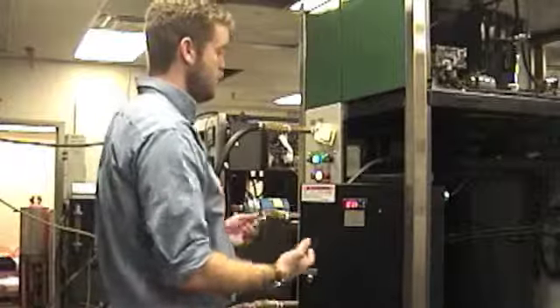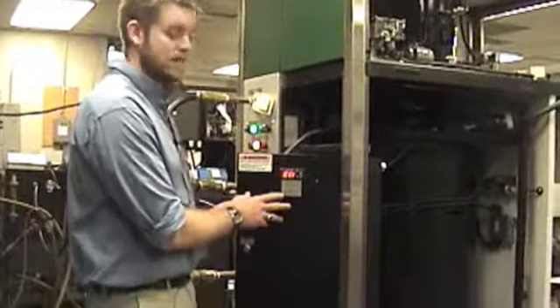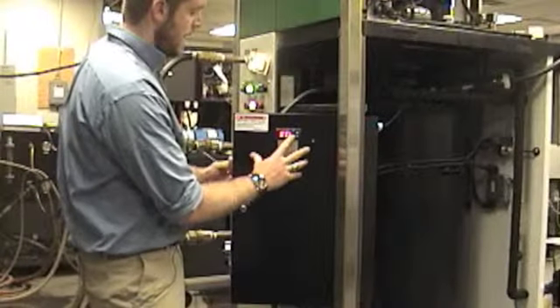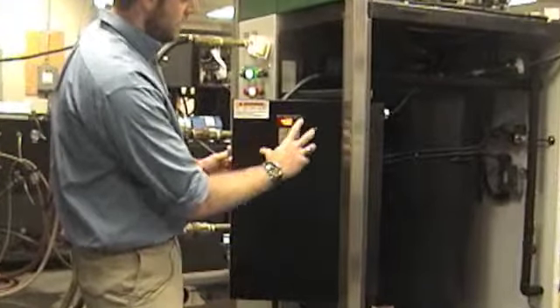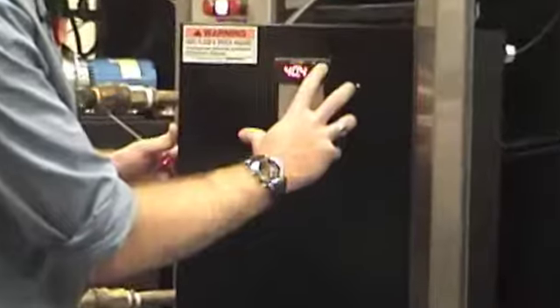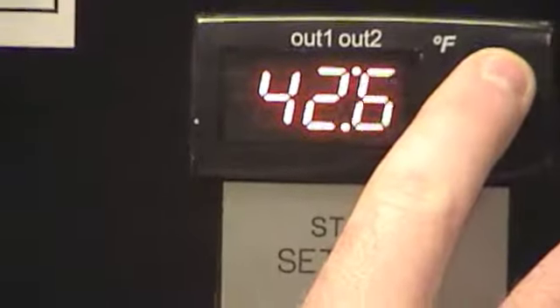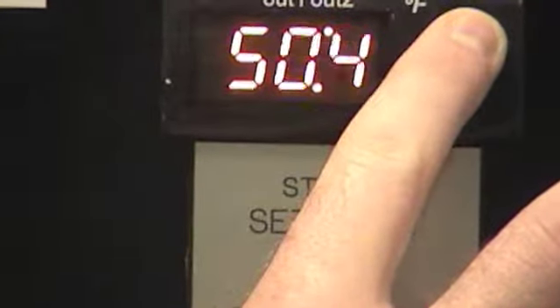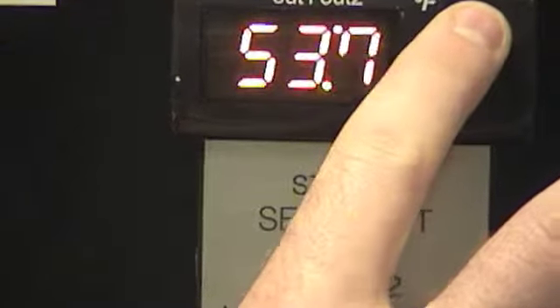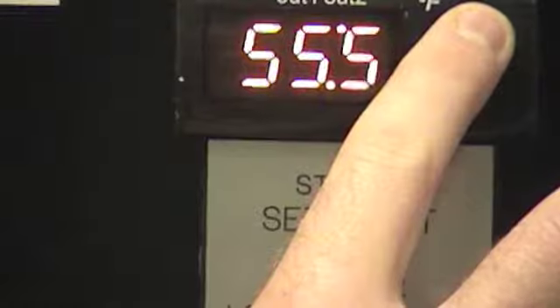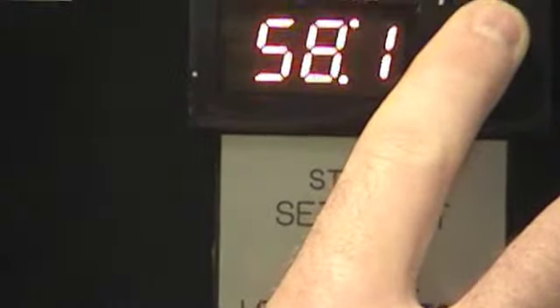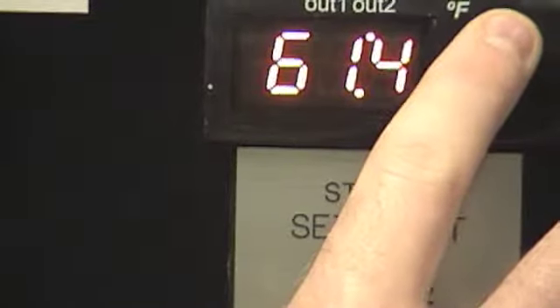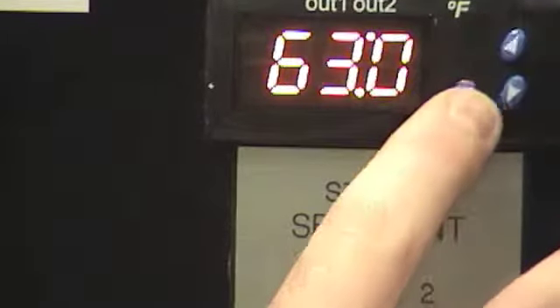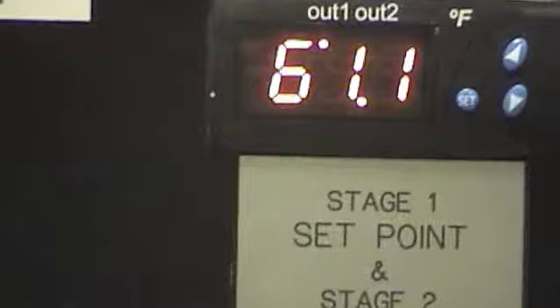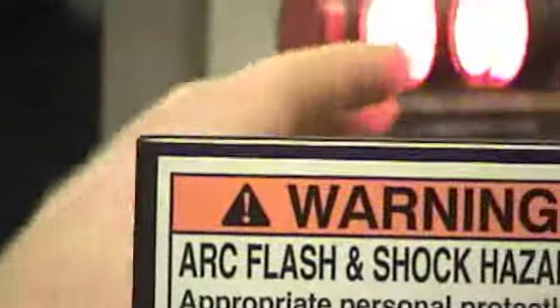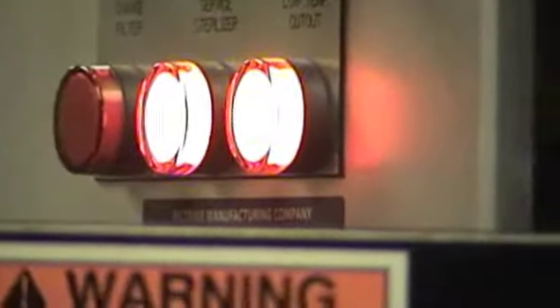So at this point, the chiller's running. It's working, so what we're going to do is test the low temp cutout on the unit. To do that, we can simulate a low temp scenario by raising the set point on the low temp cutout to above where the current water temperature is. Like so. I think we have to bring it up to about 60. And it shuts off like it should. And also your low temp alarm will go on. So that worked as it should.